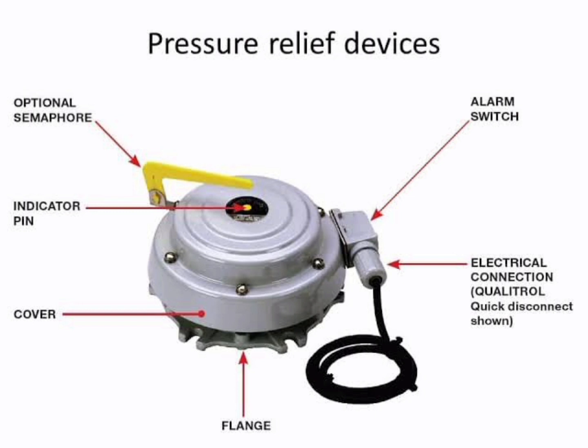The PRV operates by using a spring-loaded valve set to open at a specific pressure. When the pressure inside the tank exceeds this set point, the valve opens and releases the excess pressure to the atmosphere, closing again when the pressure drops below the set point. The set point of the PRV can be adjusted to suit the specific requirements of the transformer and the electrical power system. It is important to regularly check and maintain the PRV to ensure proper functioning. It is common practice to install the PRV in combination with other protection devices such as an oil surge relay and temperature protection to provide a comprehensive protection system.